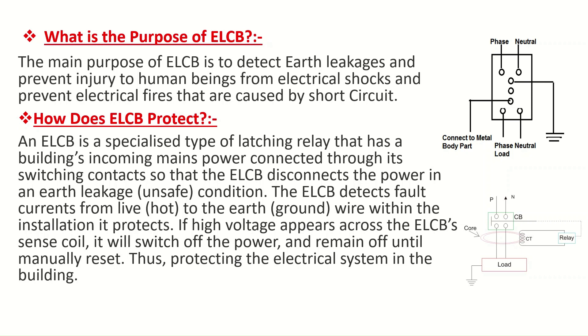How does ELCB protect? An ELCB is a specialized type of latching relay that has a building's incoming mains power connected through its switching contacts, so that the ELCB disconnects the power in an earth leakage or unsafe condition. The ELCB detects fault currents from live or hot to the earth or ground wire within the installation it protects. If high voltage appears across the ELCB's sense coil, it will switch off the power and remain off until manually reset, thus protecting the electrical system in the building.